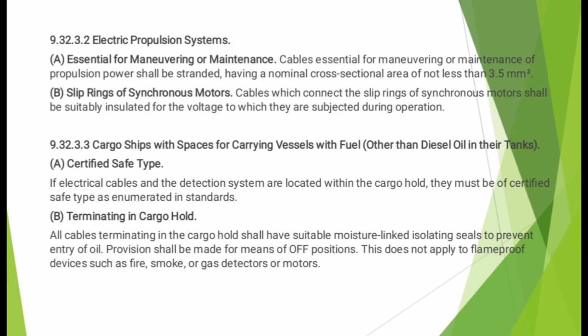9.32.3.2 Electric Propulsion Systems. Essential for maneuvering or maintenance. Cables essential for maneuvering or maintenance of propulsion power shall be stranded, having a nominal cross-sectional area of not less than 3.5 mm. Slip rings of synchronous motors. Cables which connect the slip rings of synchronous motors shall be suitably insulated for the voltage to which they are subjected during operation.